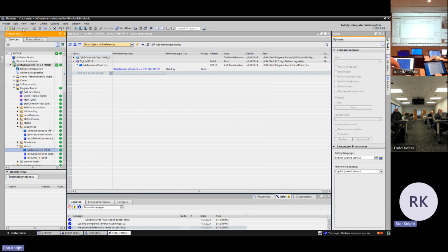I mentioned it earlier today. One of my gripes about AOIs in Rockwell is I cannot change them online. You can do exactly what we just did there. You can change a function block, download it, and it's not going to stop the processor. That is a software change. You can add inputs, you can add outputs, you can add in-outs. A little more flexible than the AOI on the Rockwell side.